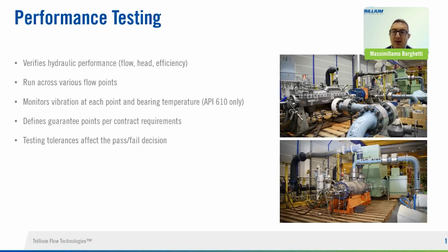We define the guarantee points as per contract requirements, and during this test, vibration is monitored at each point, and also other parameters, for example, bearing temperature. This is a special requirement by API. Finally, the point that will be described in depth later by Simon is that testing tolerance is a very, very important feature here, because it makes the difference. It is affecting the pass or fail decision for the test. Basically, the curve is the same, but considering different tolerances, you can really have the possibility to pass or fail the test according to the client requirement.